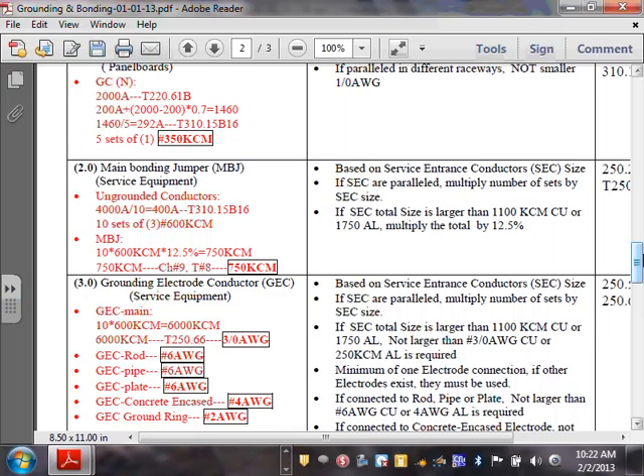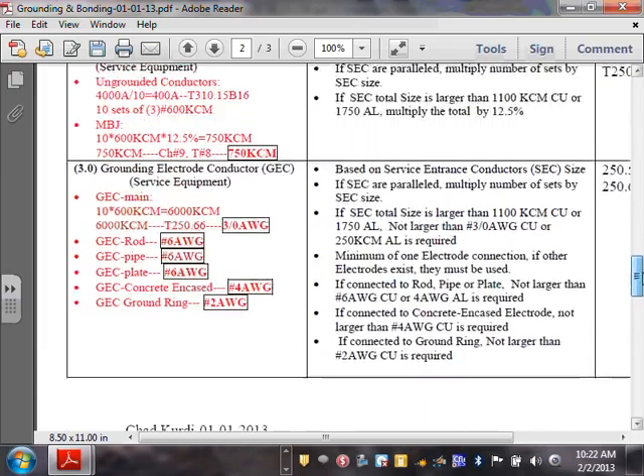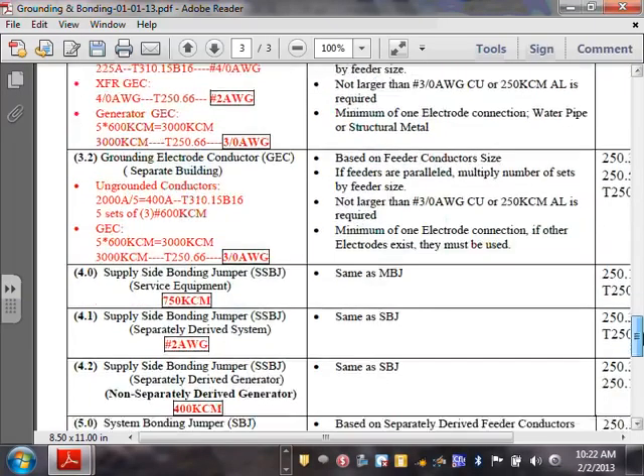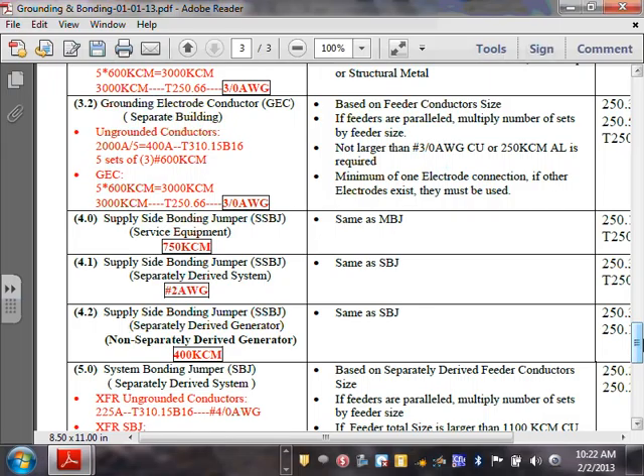You take the 600 kcm. Can somebody do it? Take the 600 kcm, you size based on the conductors in one conduit. So 600 kcm, Table 250.66. Can somebody get what the main bonding jumper would be in this case? Well, main bonding jumper, remember, it's not an issue. The main bonding is done as a copper bar. The issue becomes the conduit. Is the conduit right here number 4, the supply side bonding jumper?